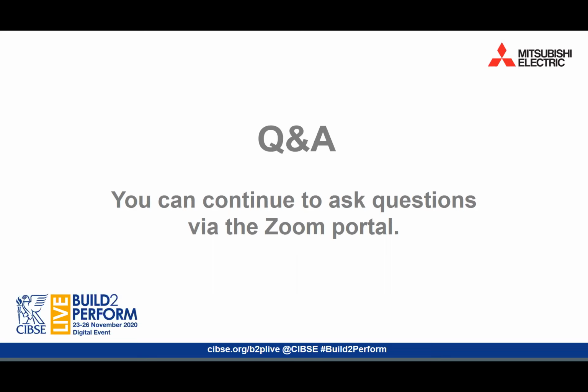So Mark Ferris asked a question, many thanks for this. Is it fair to say that in practical terms the highest return temperature is about 29 degrees, similar to the last question, I suppose? In fact, Mark, the highest return temperature that the QAHV can allow is actually 63 degrees. The unit won't go into a thermo off mode until it sees an inlet temperature of 63 degrees. So you are able to get the vessel temperature up to that temperature, so we can pasteurize that vessel every day to make sure that all of the water in the vessel has gone through that cycle. The reason to try and keep the inlet temperature below 29 degrees in periods of high demand is so that we can really utilize that large delta T, which gives us a very high COP and a very good capacity output. I hope that helps to answer that question, Mark. Thanks very much.